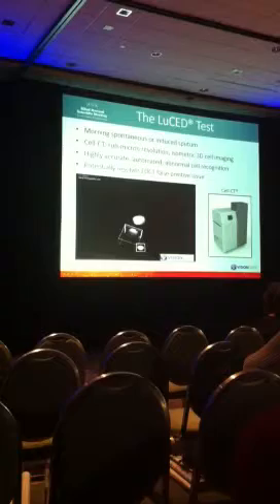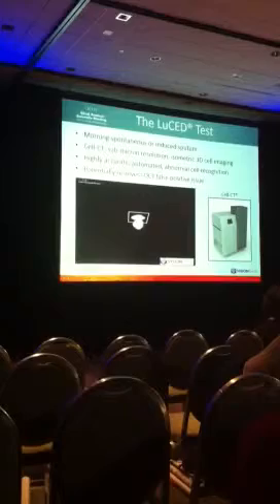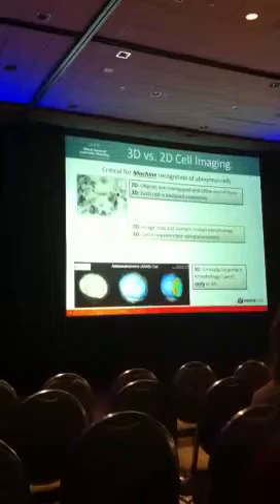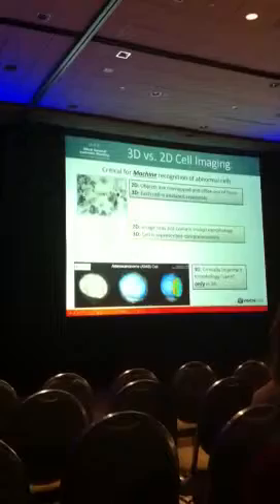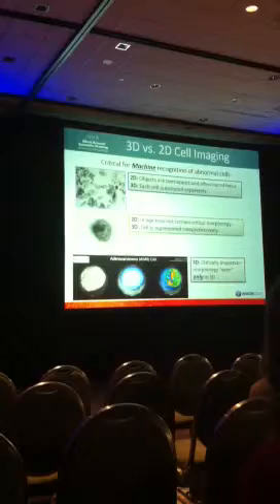This provides an image of the cell in isometric sub-micron resolution and promotes highly accurate cell recognition when the image is processed to extract features for the cell. Our system has been developed with the idea of promoting accuracy that approaches the accuracy given by human review, and that's done through three methods. First off, since the cells are processed one at a time, it eliminates overlap conditions that are often seen with microscopic slides.